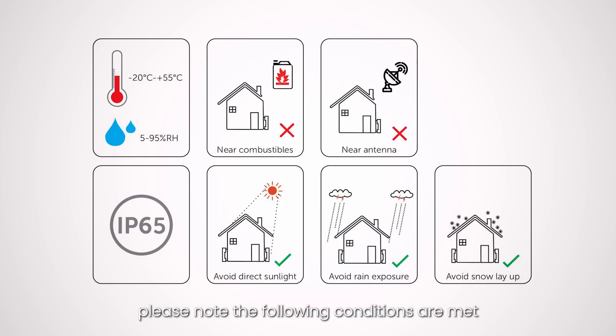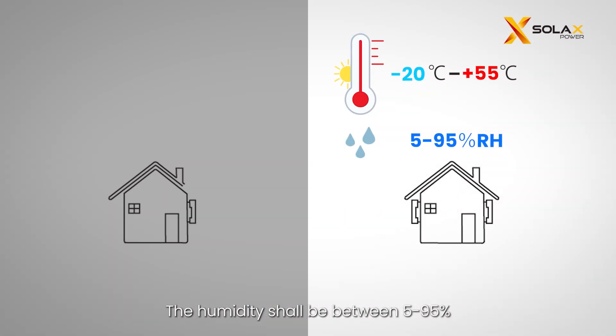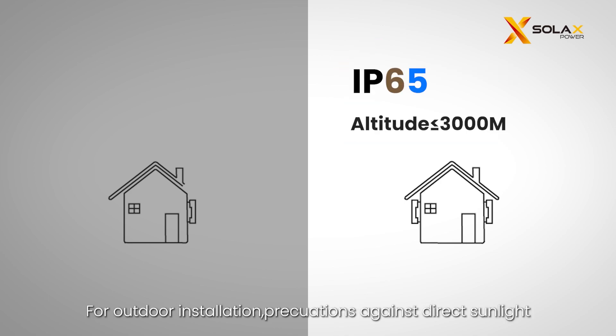Before the installation, please note the following conditions are met. The temperature needs to be between minus 20 and 55 degrees, the humidity shall be between 5 to 95 percent. For outdoor installation, precautions against direct sunlight, rain exposure, and snow layup are recommended.